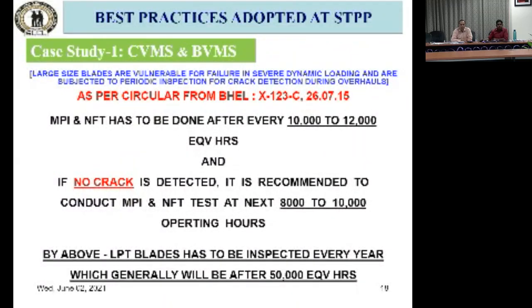To do the MPI NFT test, the turbine has to be completely dismantled, especially the LP turbine. Both rotors have to be dismantled and taken out, and the blades removed, to do the MPI and NFT. It is a big maintenance process which involves a minimum of 30 to 35 days of maintenance.